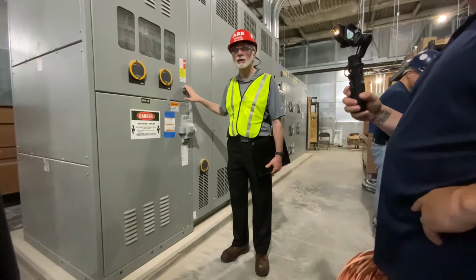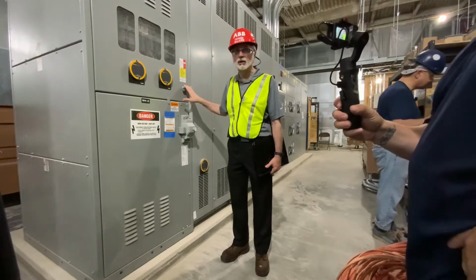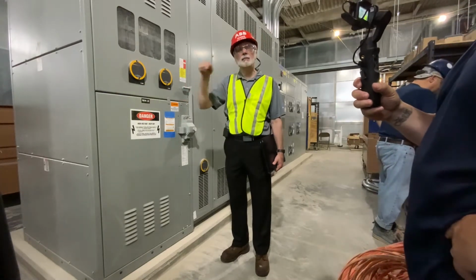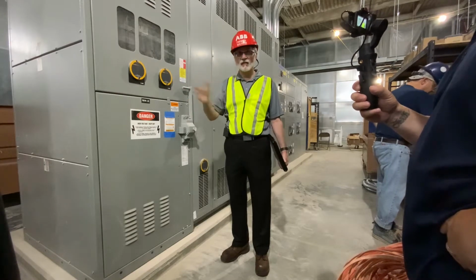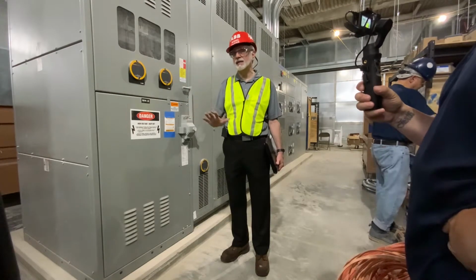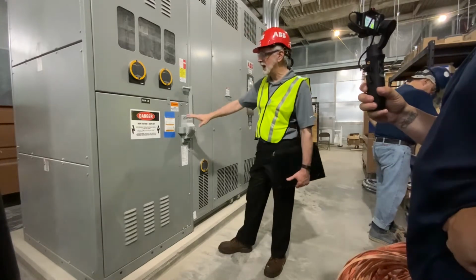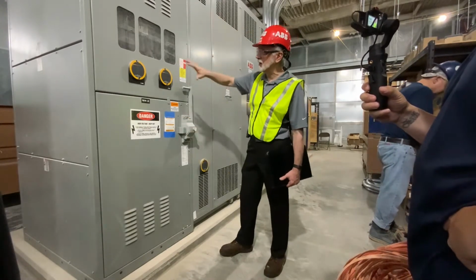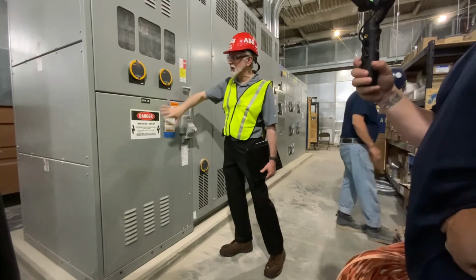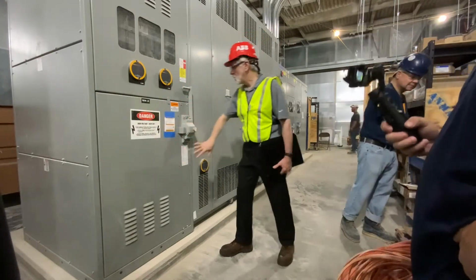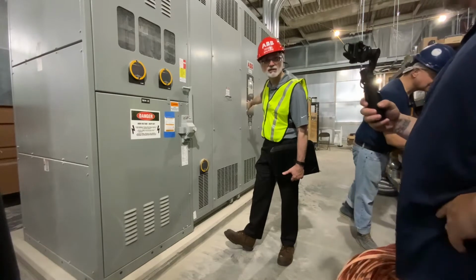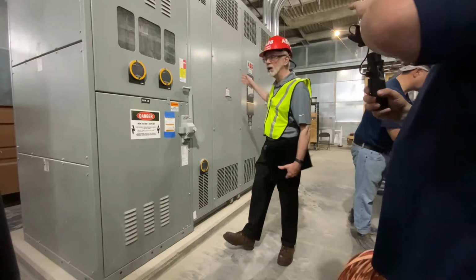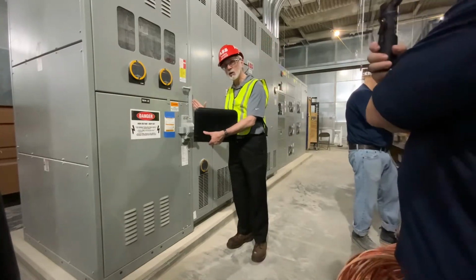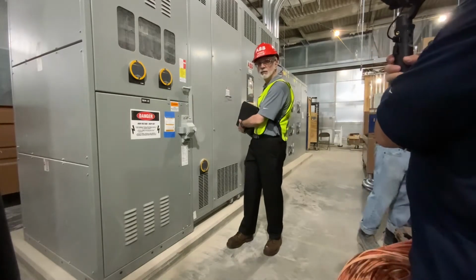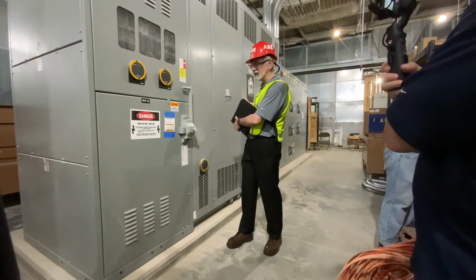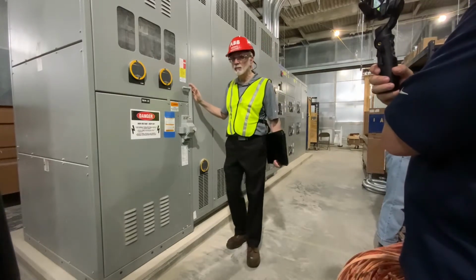This particular switch is a fused switch. So downstairs we had the mains, which were providing short circuit and overload protection for that gear down here. What we now have is the main power comes up here. We go through a disconnect switch here, which has a set of fuses, which is designed to protect the transformer, which is the next step down. So what happens is we've got 13,200 volts, and it's going to be stepped down through the transformer down to 277/480.